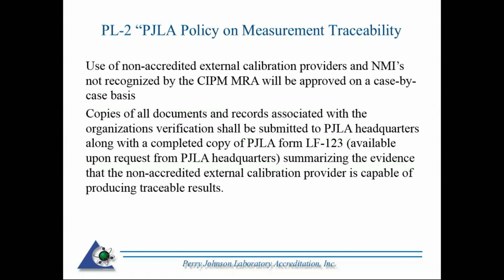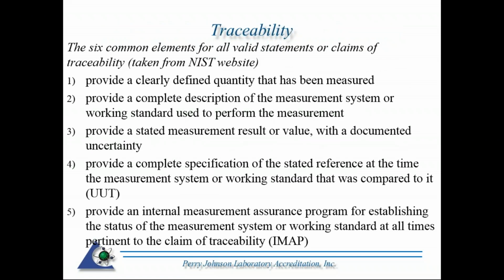So in other words, an organization can claim traceability. Sometimes it's a term that gets thrown around loosely. Our results are traceable. Like stated, if you're accredited, that's been determined by the accreditation bodies. If it's a non-accredited source, there's a little bit more work there, other than the logo, as far as the review of traceability. So we're going to look at what we require on the LF-123, the 6 elements of traceability, which is taken from the NIST website.